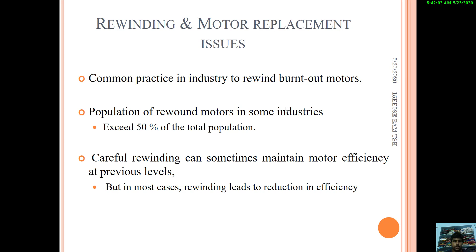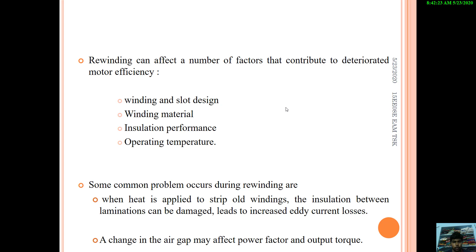Some common problems during rewinding are: when heat is applied to strip old windings, the insulation between laminations can be damaged, leading to increased eddy current losses. A change in the air gap may affect power factor and output torque. If proper measures are taken, motor efficiency can be maintained after rewinding.